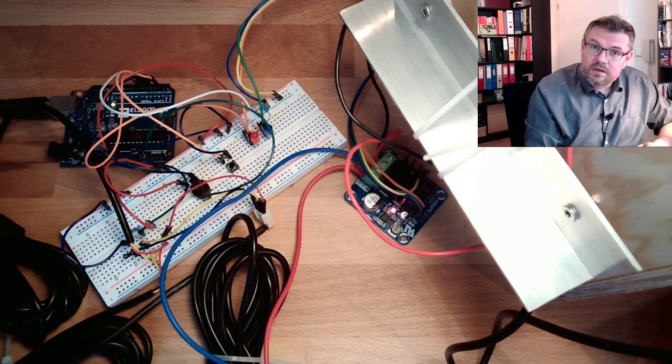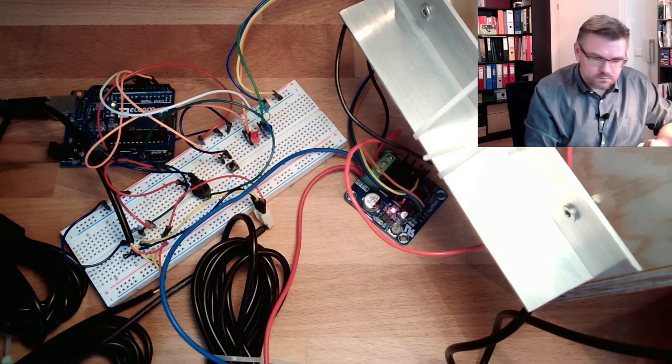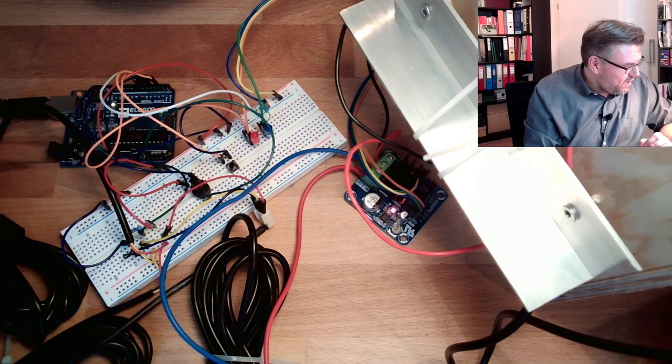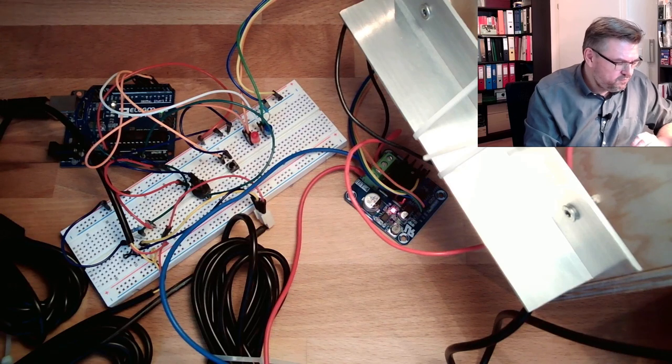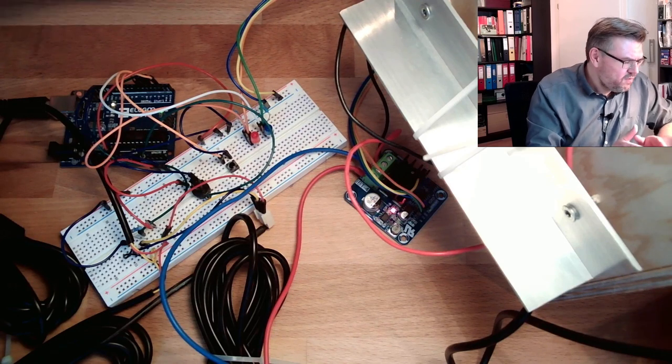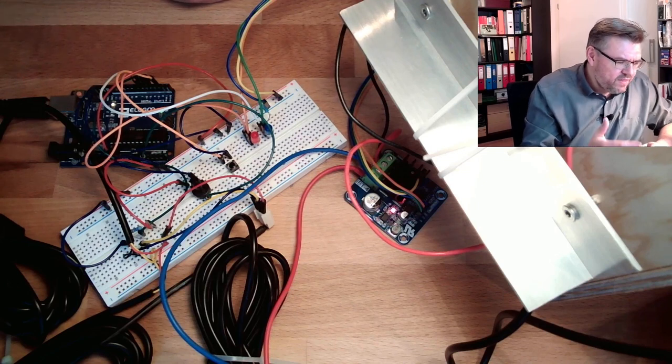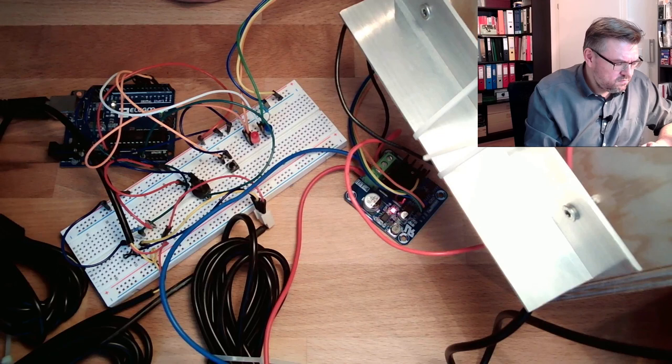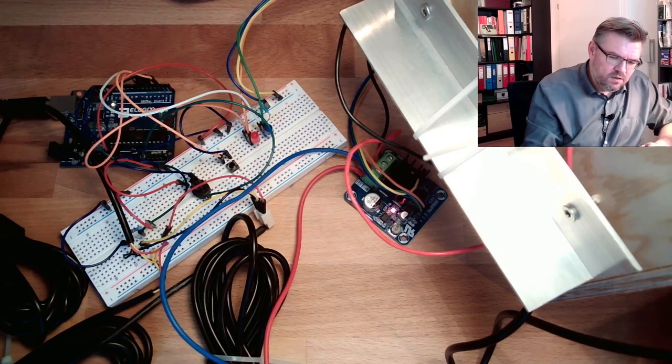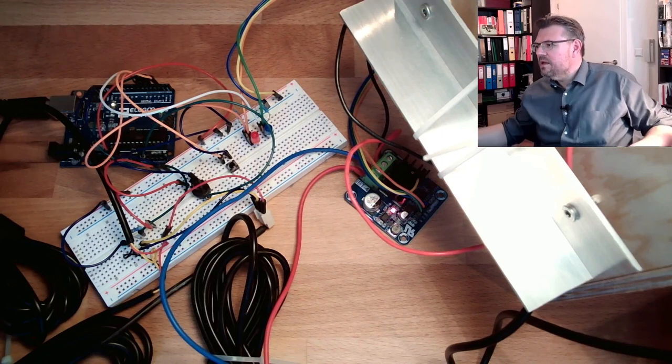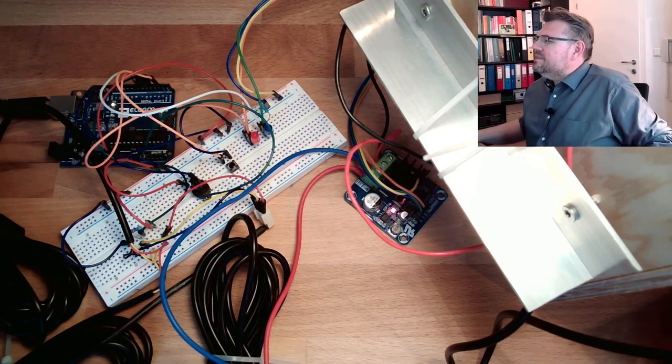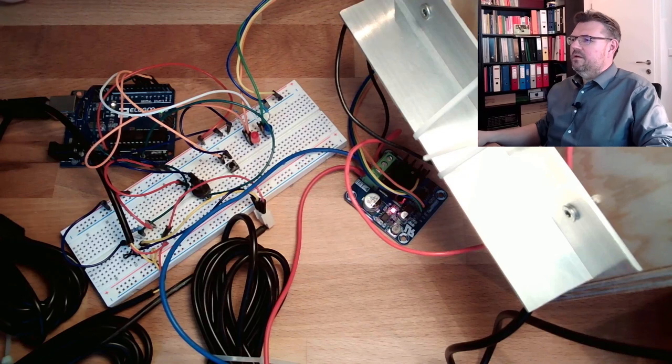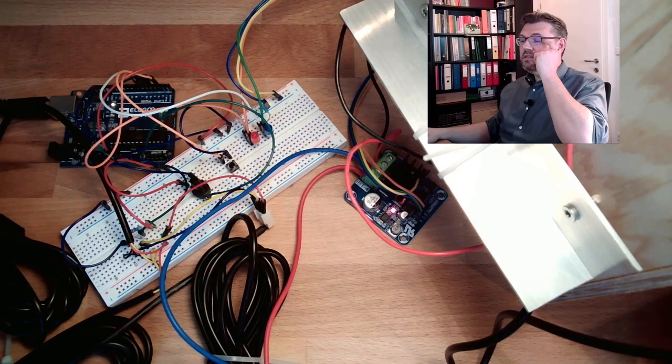The controller is just measuring the temperature of this part and getting the set point and is doing its stuff. Its stuff is a P-controller. I had programmed a P-controller, pretty simple. Just build the difference between this and the set point and this is the value we put out to the heating element. So let's have a look at what is the current status.